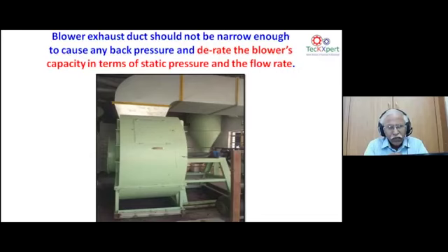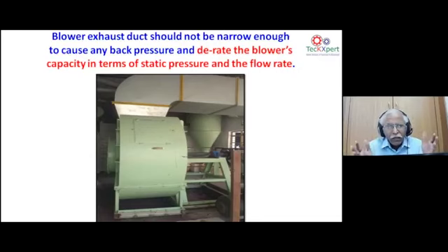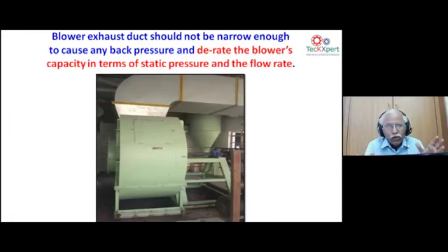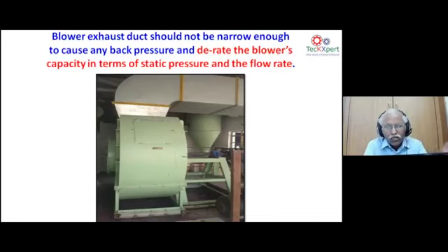Instead, expand the exhaust duct — if it's 2×2 feet, make it 2×3 feet — and take it outside in a way that back pressure is not allowed to increase. During operation, keep back pressure at a minimum so that the full static pressure — both velocity pressure and total static pressure — is utilized in the existing system.